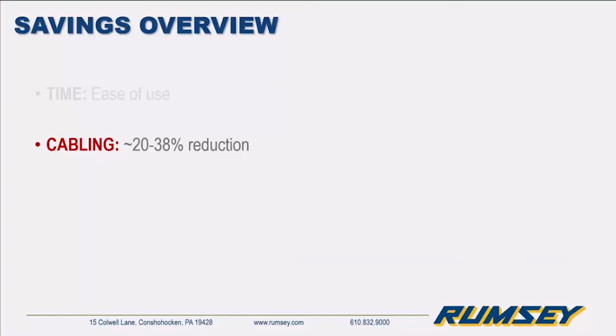From a cabling perspective, it really provides you the ability to save a lot of money. Not only are you saving money from the actual devices themselves being cabled, but you don't have to home run a wire back to a safety relay or an input card. So significant savings there if you want to reduce your I/O count. In the past, people typically used distribution blocks to wire to, and then you're running maybe an 18 or a 23 wire cable back to an I/O card. With GuardLink, you don't have to do that. You really just have one input going into that DG relay connecting over Ethernet, really saving you a significant amount of money on cabling.